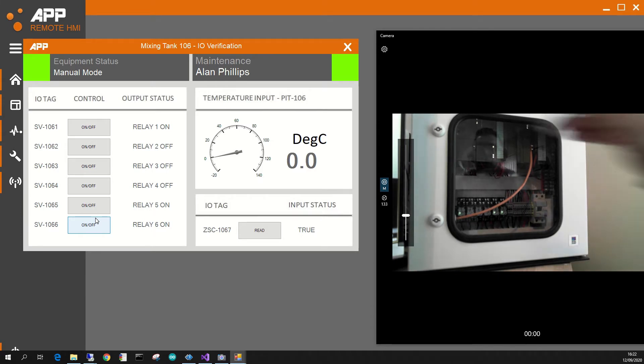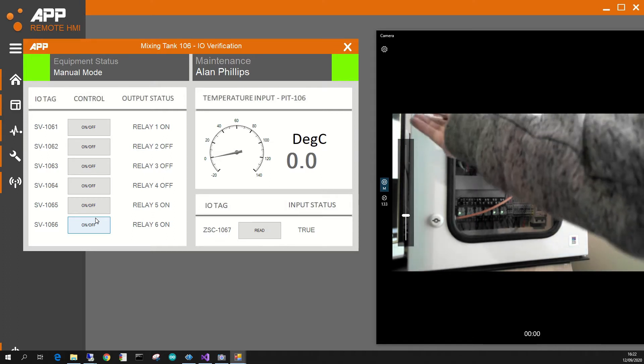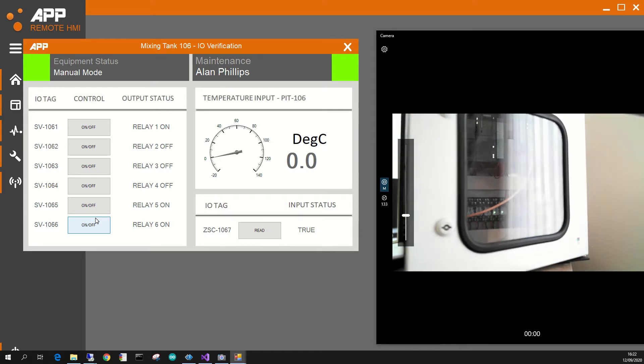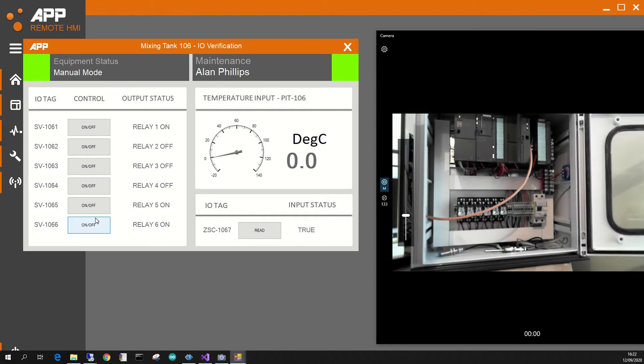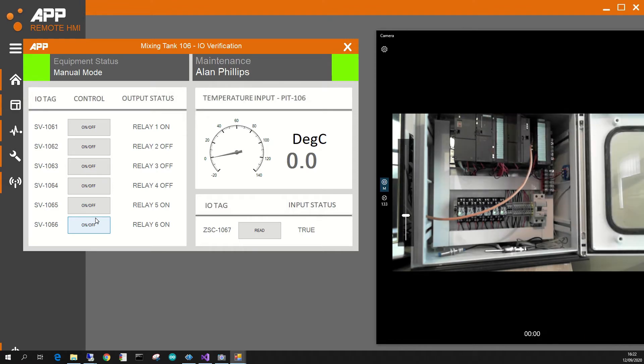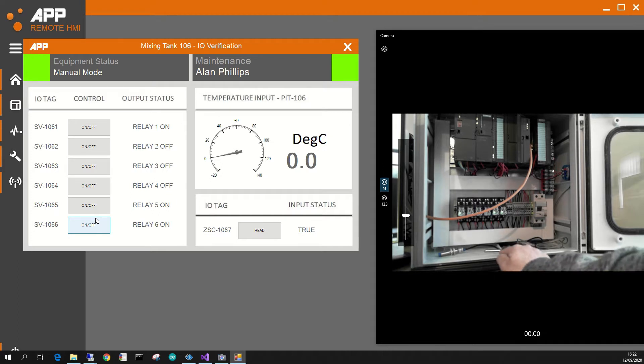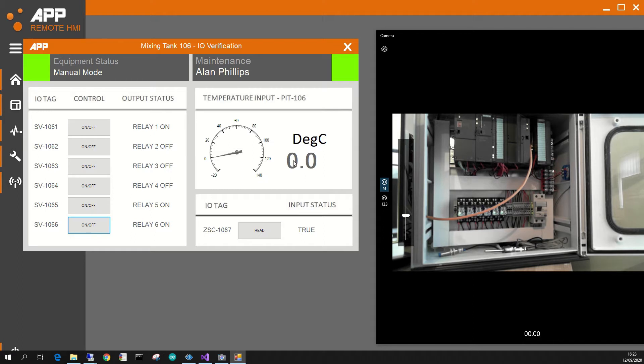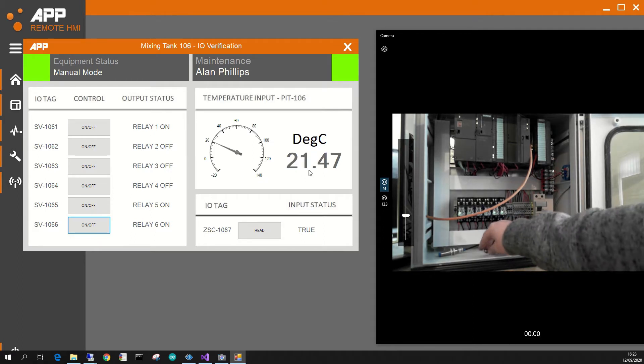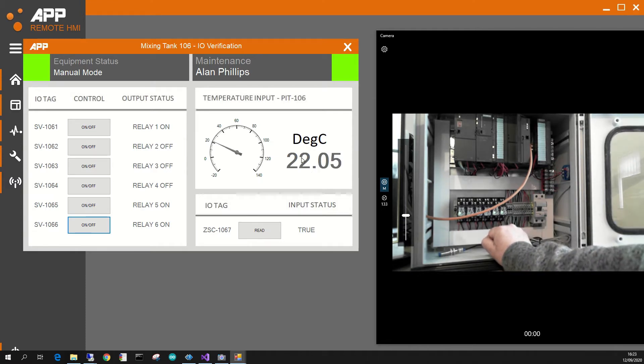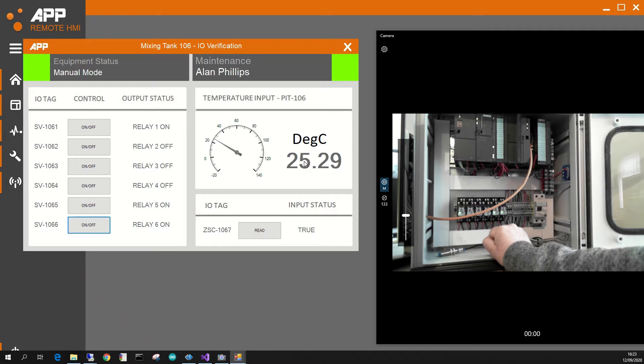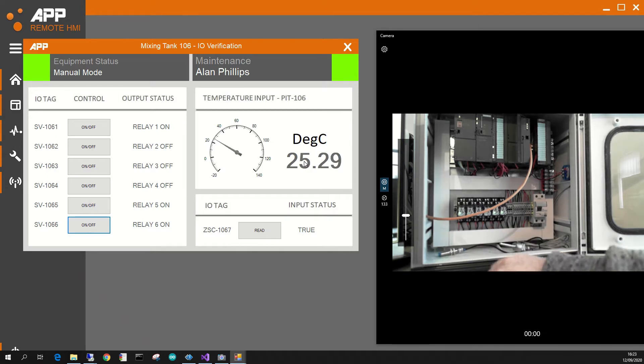Just as an example, there's bits being written there and you can see that the PLC is turning on and off. And if I just open up the cabinet, what's also inside is there's a digital input up here just being read from a proximity switch. So if I want to get, say this is a PT100 as well for an analog, if I just give it a click, I can see it's 21 degrees. And then if I just hold on to it, we'll see that the temperature is going to gradually go up because I'm actually holding it in my hand. So it's just going up and up and up just because the temperature.